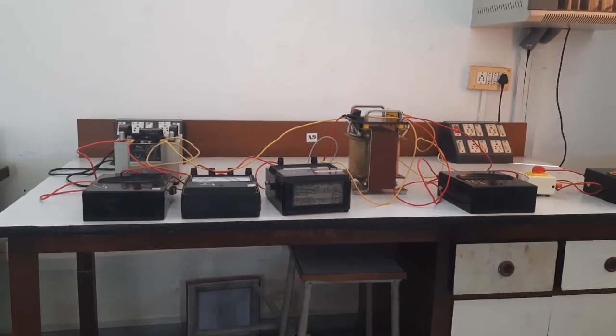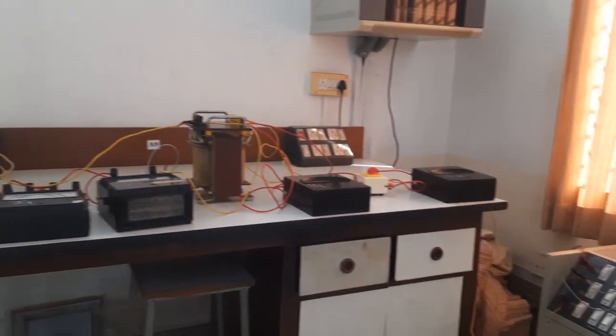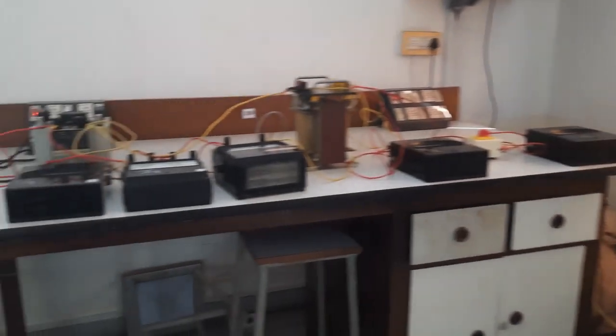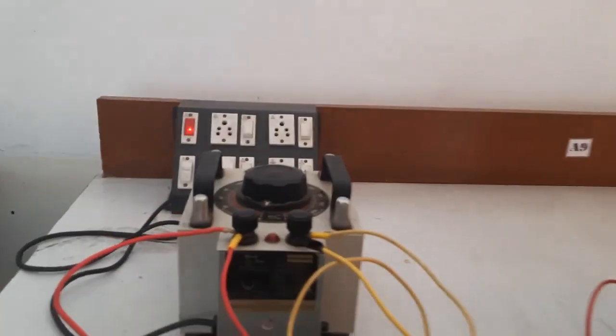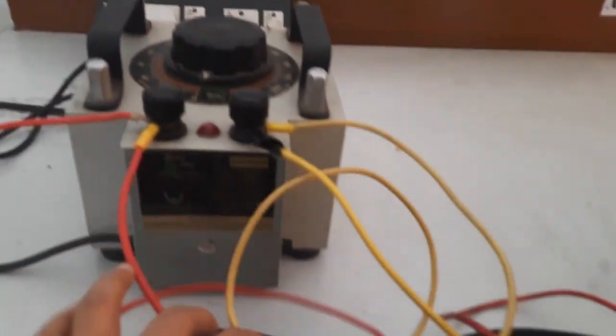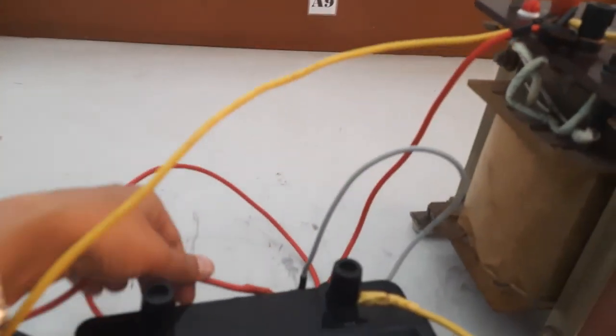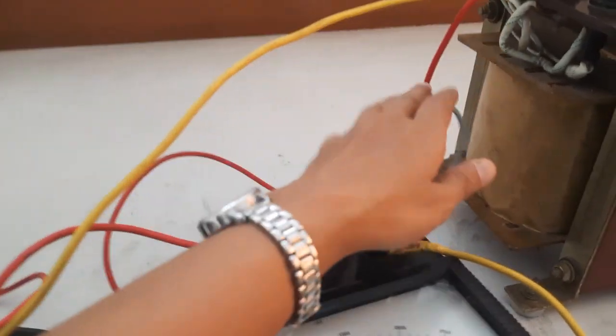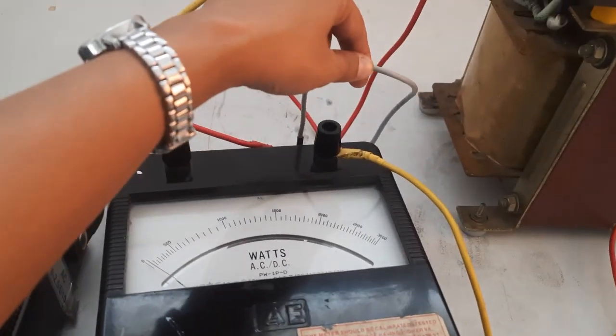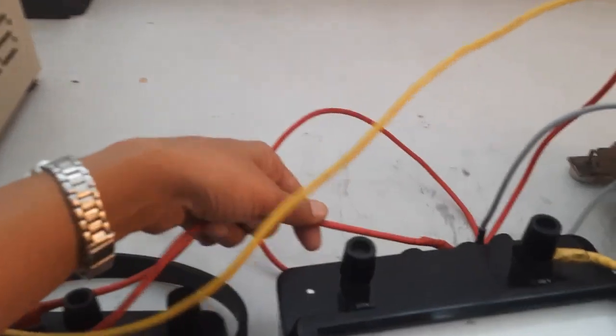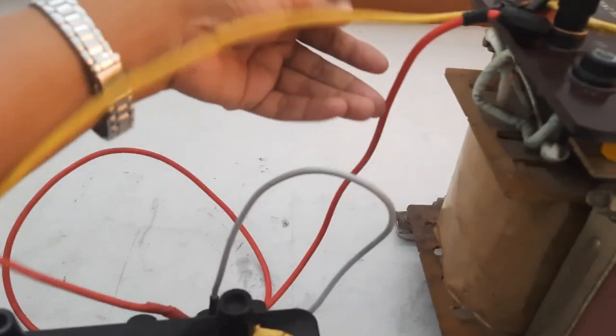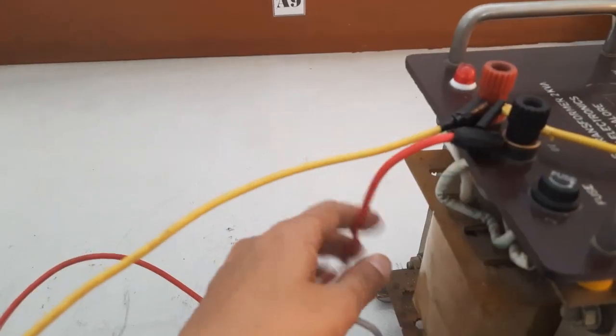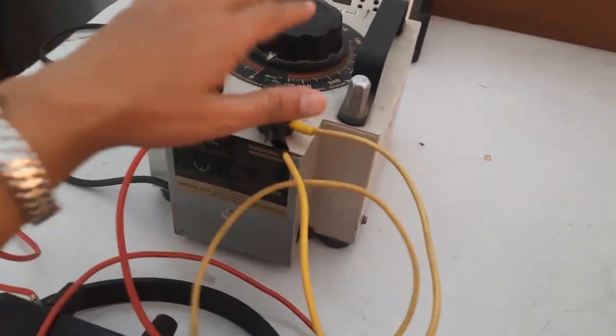You can see the circuit connection as shown in the circuit diagram. From the auto transformer terminal, connection has to be given to the ammeter. From the ammeter, the connection has to be given to the wattmeter M terminal. M and C terminals of the wattmeter should be connected. From the L terminal, the connection has to be given to the 0 of the transformer. Next, from 230 volt, the connection has to be given back to the auto transformer.